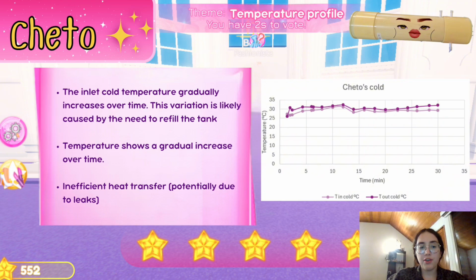For Cheto's behavior, first, the inlet temperature of the cold fluid gradually increases over time, and this variation is likely caused because we needed to constantly refill the tank, which introduces colder or warmer water depending on the ambient or supply conditions. Despite these fluctuations, it stabilizes near 30 degrees after a few minutes. The outlet cold temperature is slightly higher, which is expected in a heat exchanger because it indicates heat absorption from the hot fluid. However, the temperature difference between the inlet and the outlet is not substantial, which suggests either inefficient heat transfer, potentially due to leaks, or insufficient temperature gradient between the fluids.